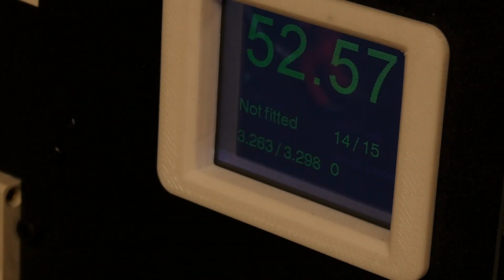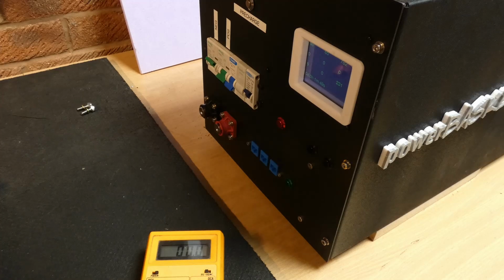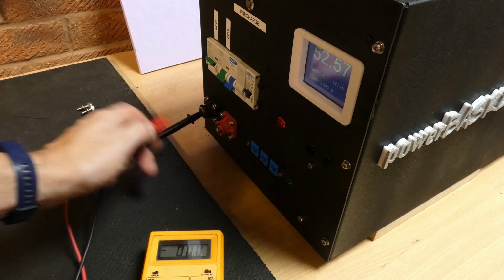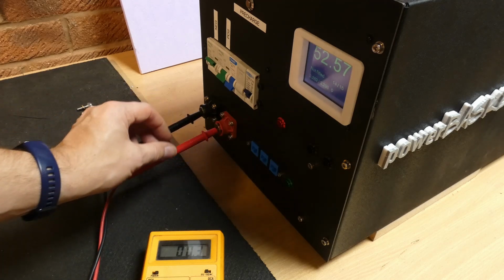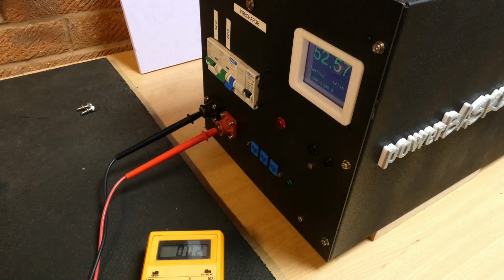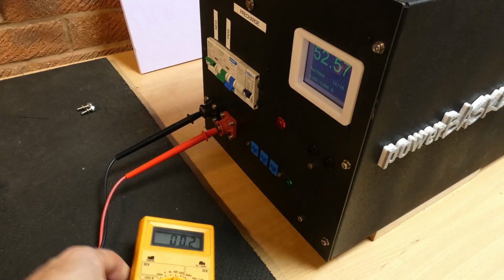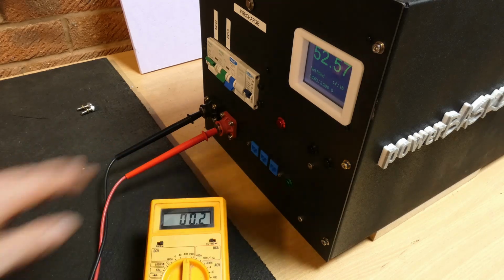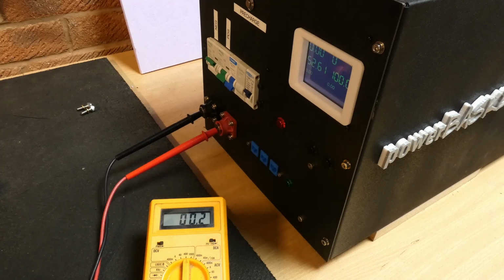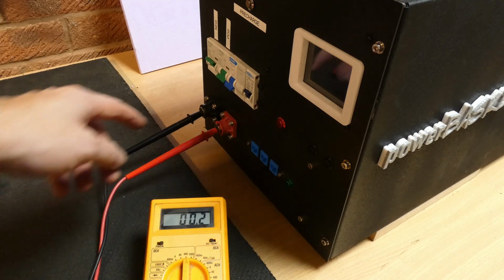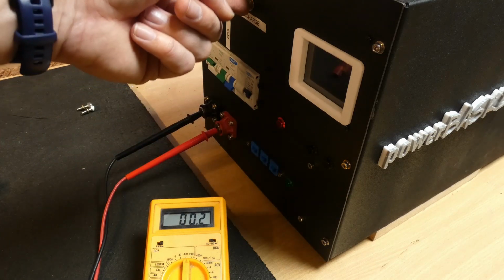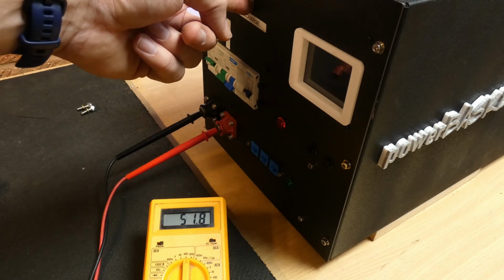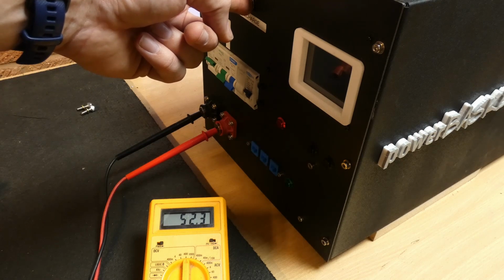And obviously no current or anything like that, so that's looking really good. Now the other thing we need to check is the voltage on the output. That should be 0, or it's near enough at the moment, so there should be no output right now, which is what that's telling me. We've got a pre-charge button, so if I press that, we should get the full voltage on the output, which we do.